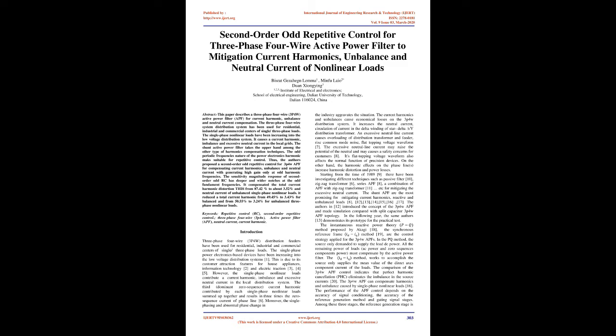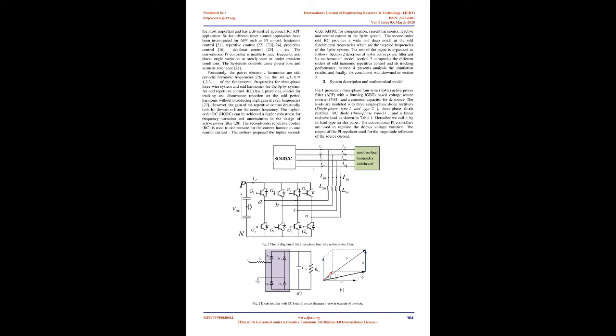The third, dominant zero sequence, current harmonic contributed by each single-phase nonlinear load sums up together and results in 3 times the zero sequence current of the phase line [6]. Moreover, the single phasing and abnormal phase change in the industry aggravates the situation. The current harmonics and unbalances cause economic losses on the 3P4W distribution system. It increases the neutral current and the circulation of current in the delta winding of the star delta/Y distribution transformer.